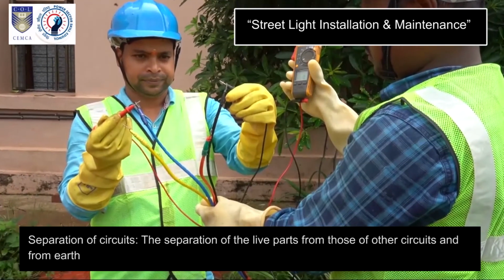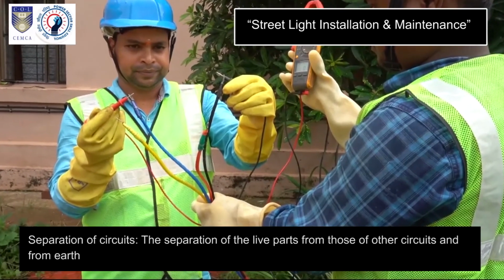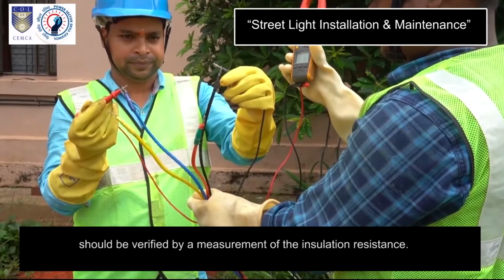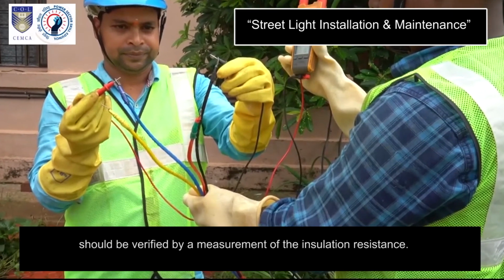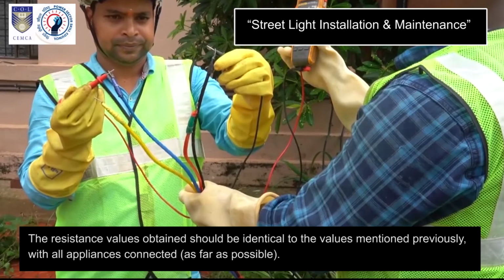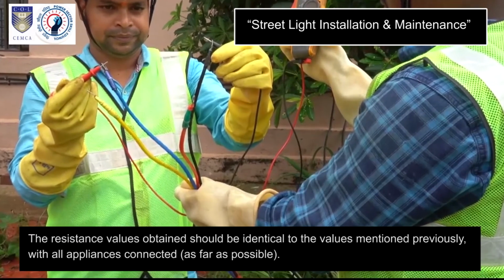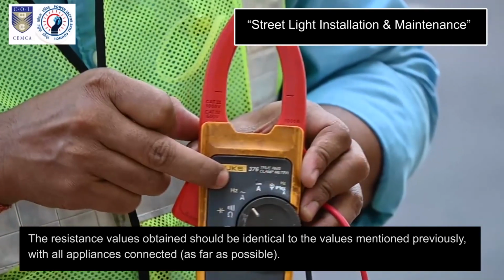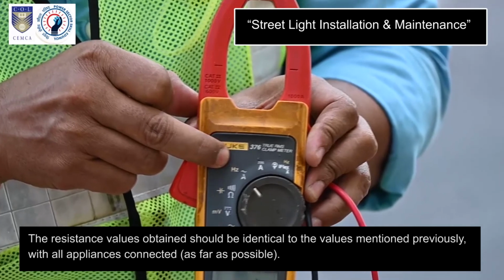Separation of circuits. The separation of the live parts from those of other circuits and from earth should be verified by a measurement of the insulation resistance. The resistance values obtained should be identical to the values mentioned previously, with all appliances connected as far as possible.